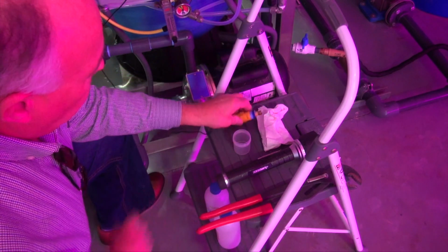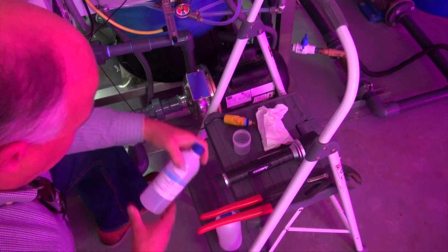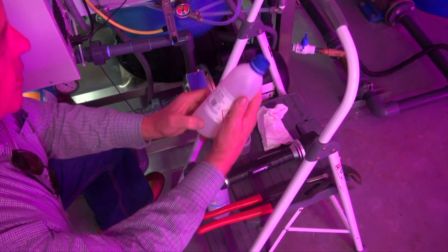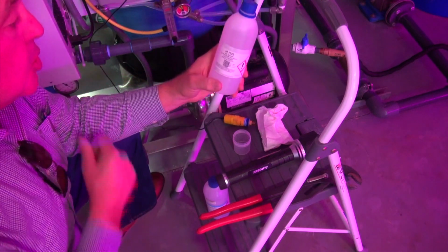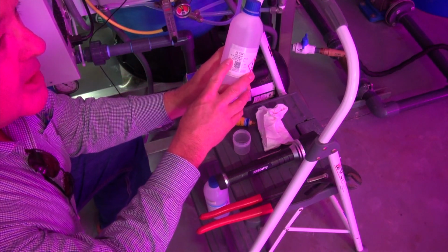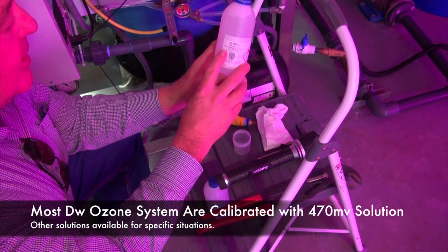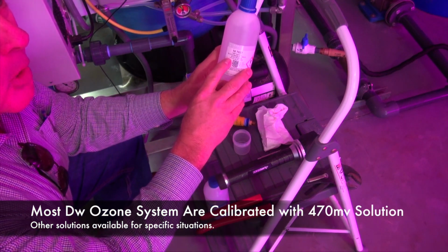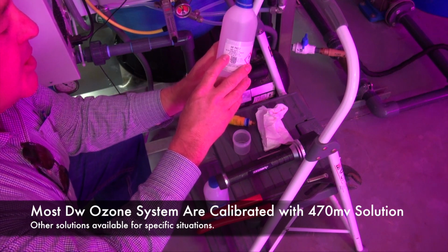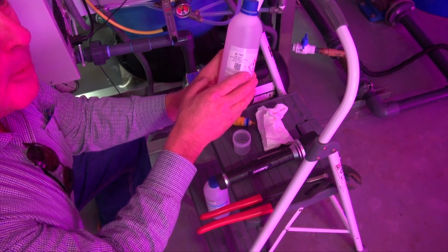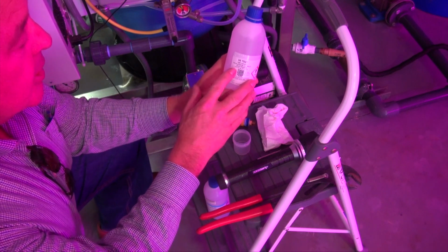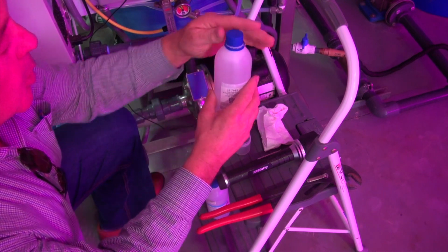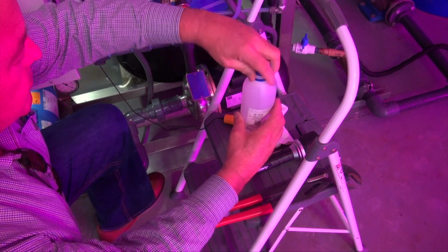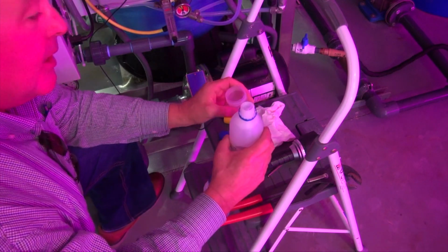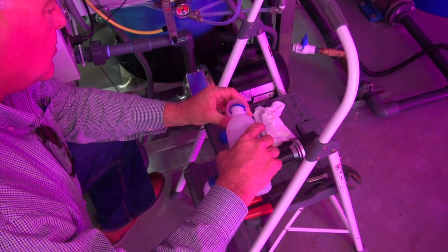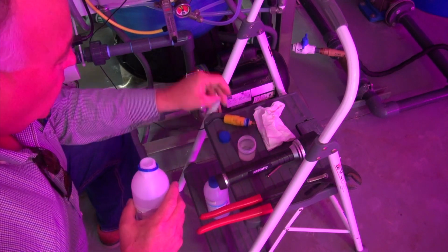So let's assume that we've cleaned that ORP probe up. Now we pull a solution. We have two solutions to choose from. This one is a 470 millivolt solution. I picked that because we generally run around 470 to 500 millivolt on this system. There's also a 240 millivolt solution that we can use. For a simple calibration, we're just going to use the 470 millivolt solution. We're going to pour it in a small cup so that we don't waste it.